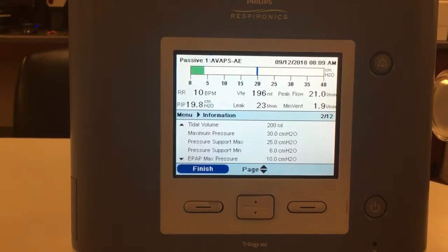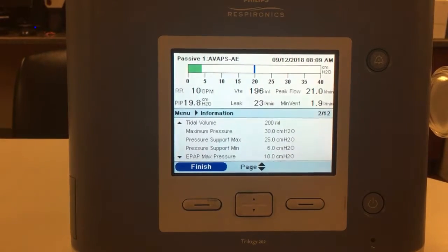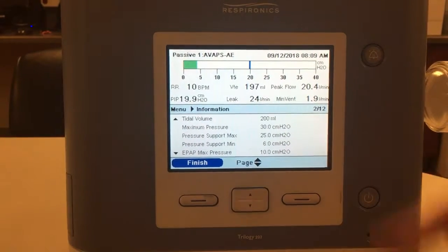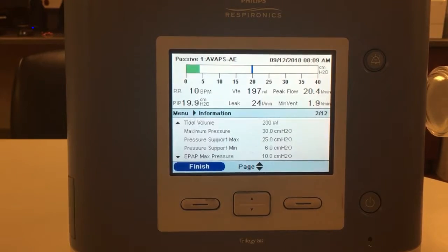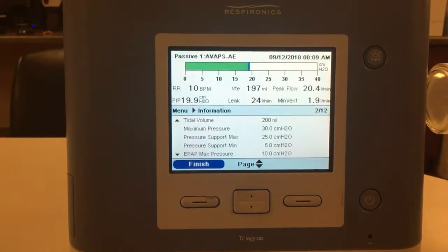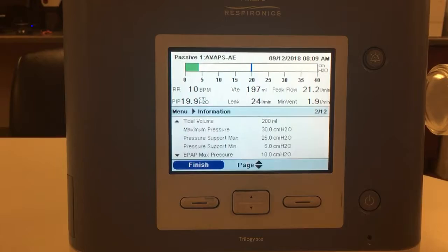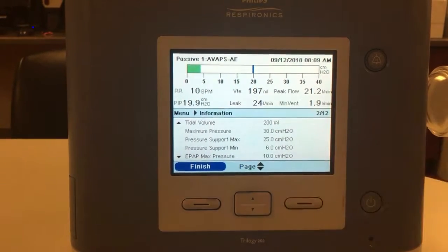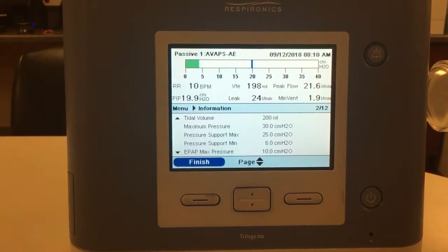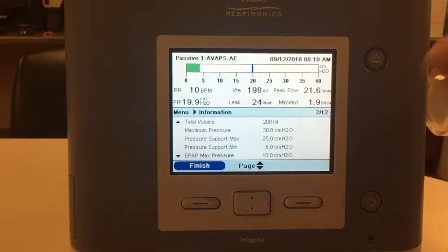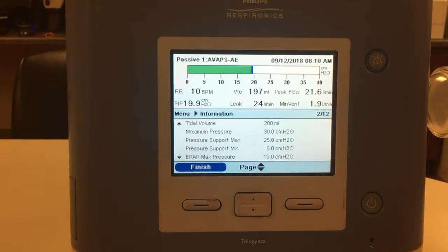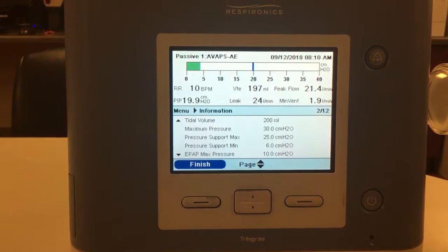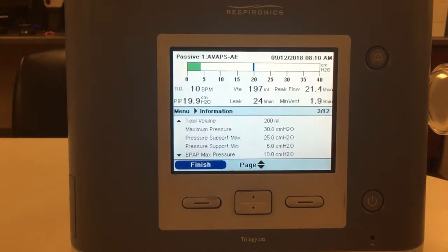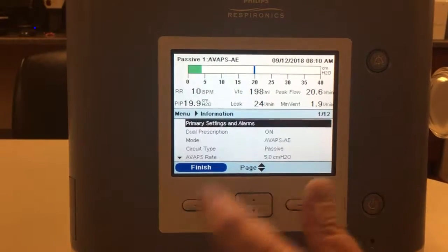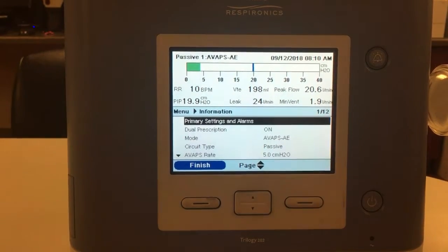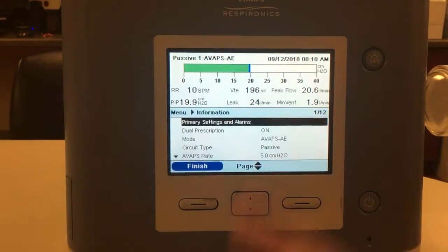So whether it's positional or so, if the patient turns on their back and the patient requires more pressure to get in the tidal volume, to get in the 200 milliliter tidal volume, the machine will adjust, increasing the pressure. Now, an AVAPS rate of 1 will be a 1 centimeter water pressure increase per minute to get the tidal volume to where it needs to be. An AVAPS rate of 5 will be a 5 centimeter water pressure increase to get to where that tidal volume will be. Also, just in case the tidal volume starts shooting over its set value, the 200 mLs, the pressure will also come down to maintain that tidal volume. And once again, the AVAPS rate will be just that: the speed at which the ventilator adjusts to keep the set tidal volume.